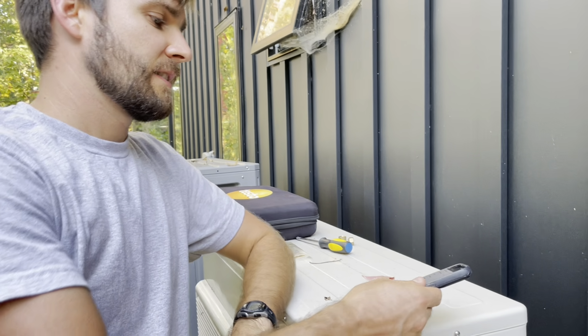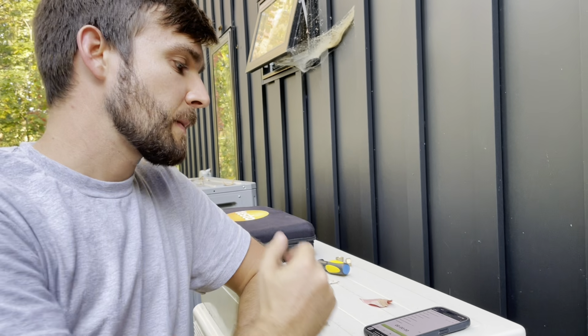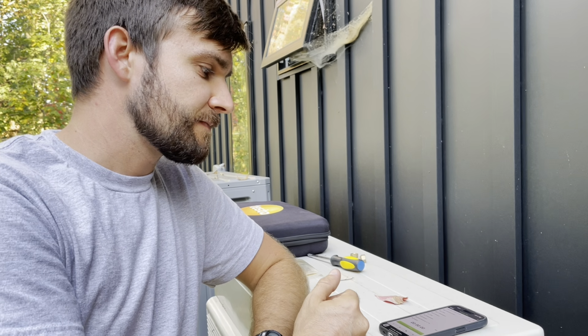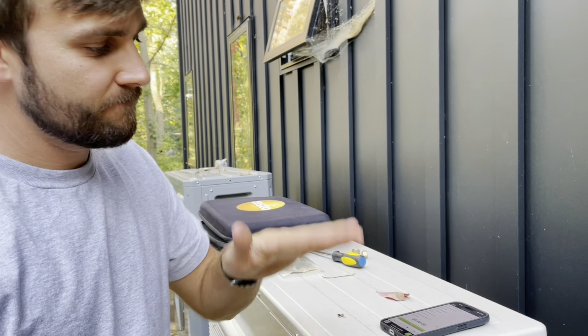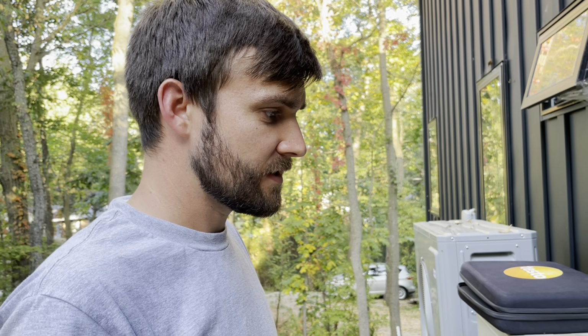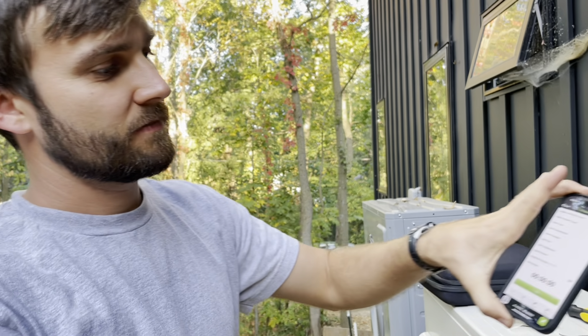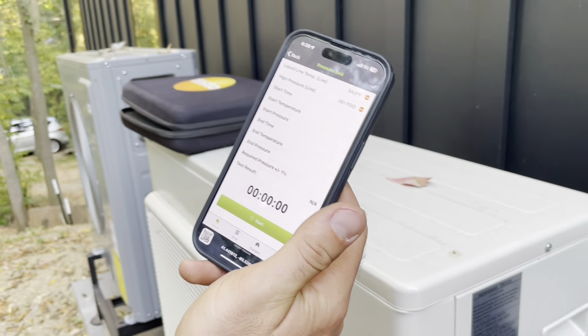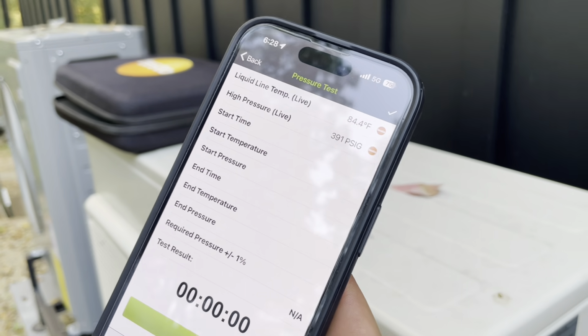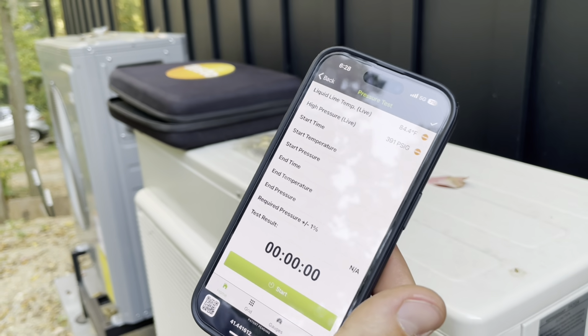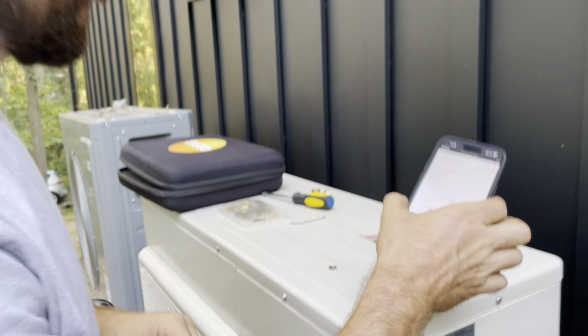Well, it's going down. This was in my hot van, so I've got to let it acclimate to the temperature of the line. And then we'll start the pressure check. How long's it got to be? 10 minutes once I start. So once that temperature kind of reaches equilibrium. How much fluctuation is okay? Fluctuation? In nitrogen, like 0? You want it to move 0? Plus or minus 1%. So not a ton. So 4 PSI, no more than 4 PSI.